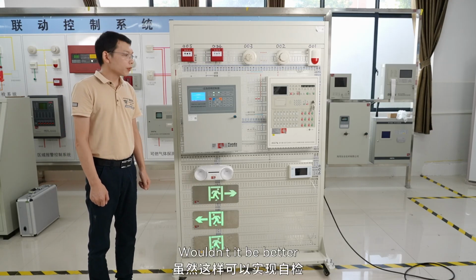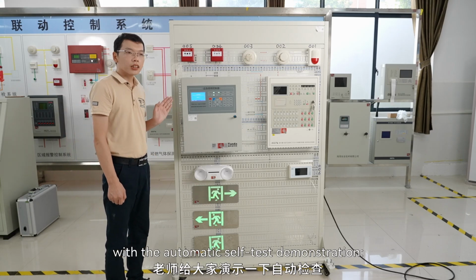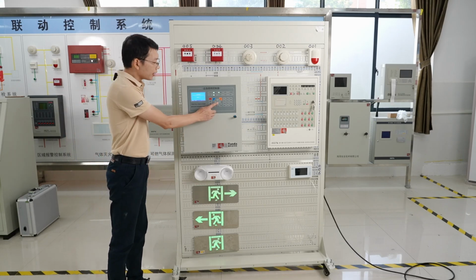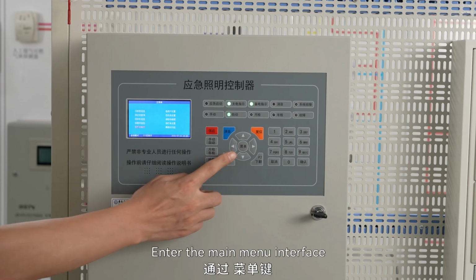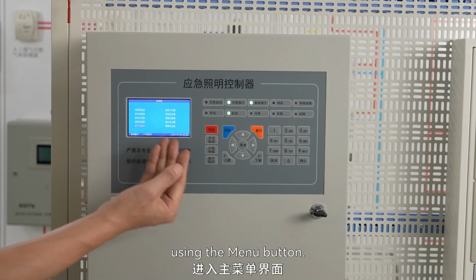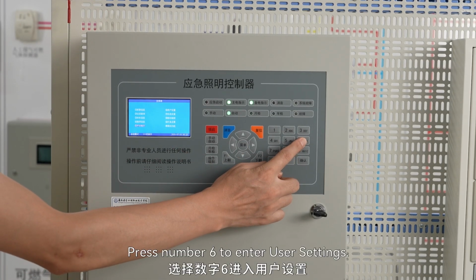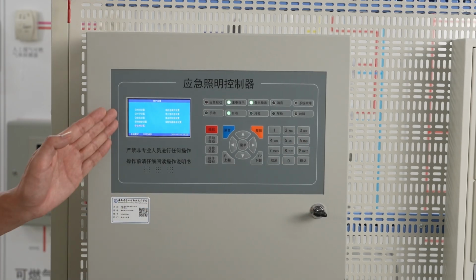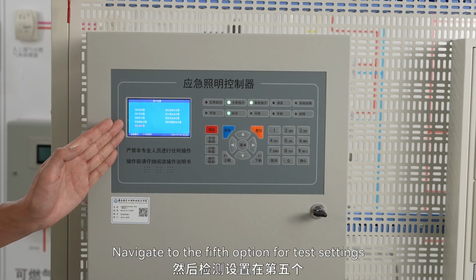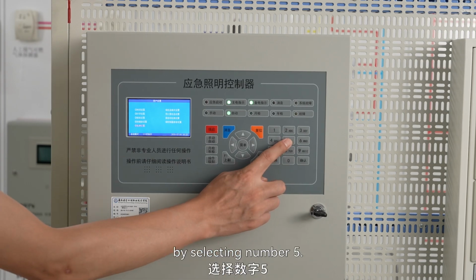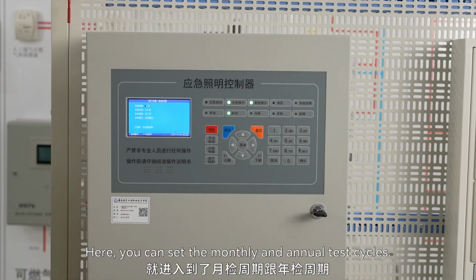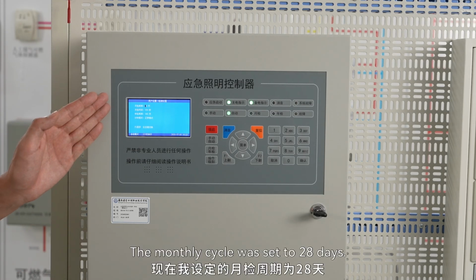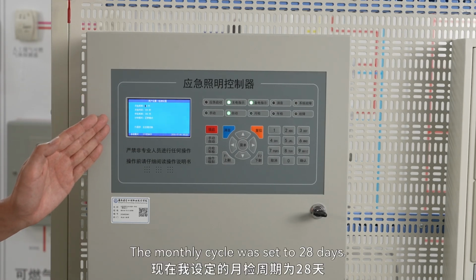Wouldn't it be better if we could perform an automatic self-test? Let's proceed with the automatic self-test demonstration. Enter the main menu interface using the menu button. Press number 6 to enter user settings. Navigate to the 5th option for test settings by selecting number 5. Here, you can set the monthly and annual test cycles. The monthly cycle was set to 28 days.